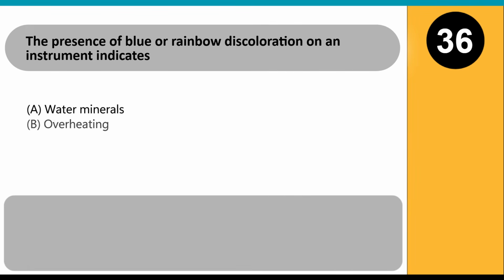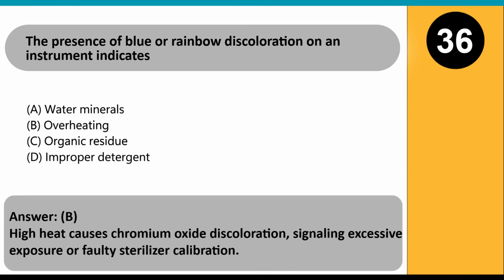The presence of blue or rainbow discoloration on an instrument indicates: A. Water minerals. B. Overheating. C. Organic residue. D. Improper detergent. Answer B. High heat causes chromium oxide discoloration, signaling excessive exposure or faulty sterilizer calibration.